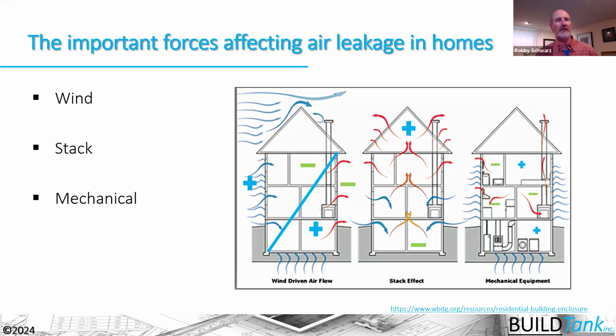And you can see I've drawn a line diagonally across the house. So on the windward side of the house, we have a positive pressure, and the wind is actually going to blow air through holes in our building envelope there. And remember, a typical outlet box has about a net free area of 1 square inch of hole area if we don't seal that up. And so the code is asking us to actually seal that up.